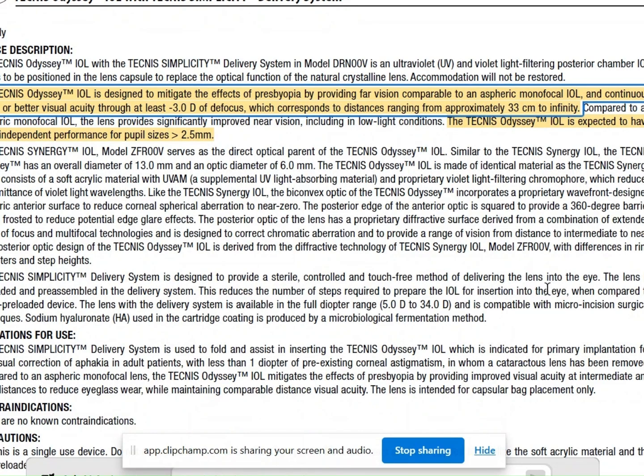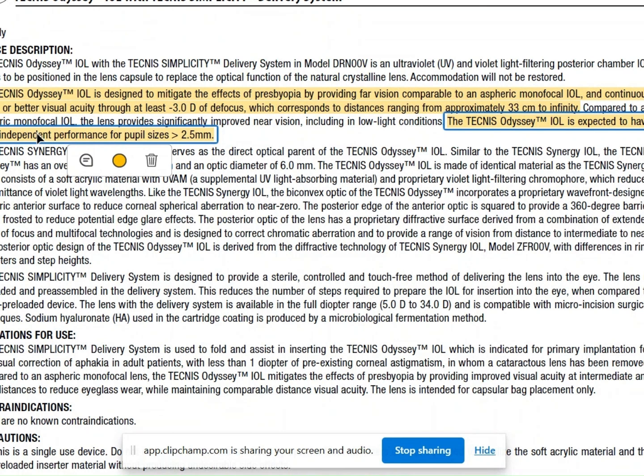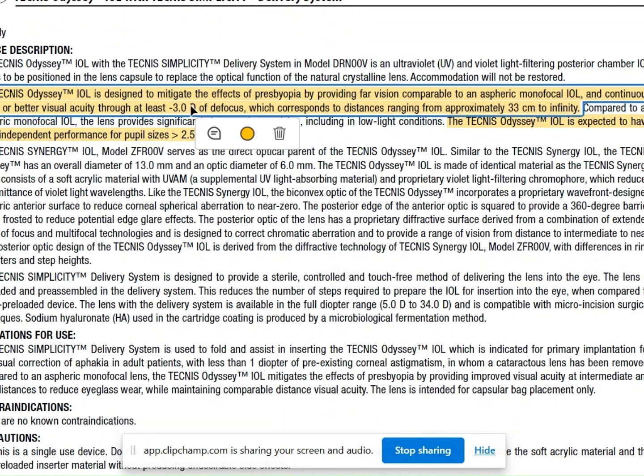This is the IFU, or DFU, that comes as a product insert in the box. The TECNIS Odyssey IOL states that it should work as pupil-independent for pupil sizes over 2.5 millimeters. The other information provided is that patients are expected to achieve 20/32, that is 0.3 logMAR or better vision, from 33 centimeters — a reading distance — to infinity.